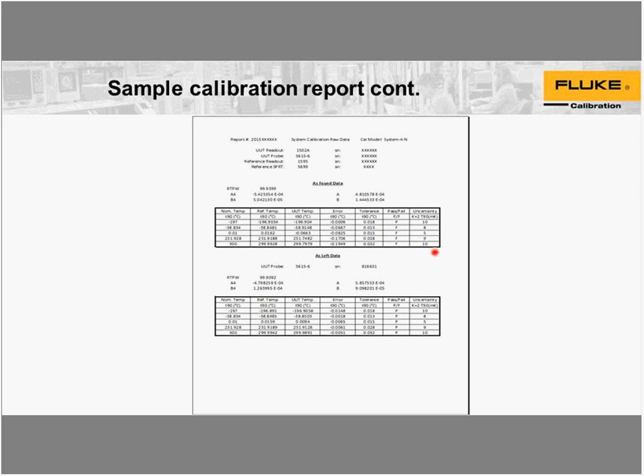So you know that by how measuring, we have a 10 millikelvin uncertainty at minus 200. We have an 8 millikelvin uncertainty at minus 38. We have a 5 millikelvin or millidegree uncertainty at 0 degrees. And then we have 9 and 30, or no, what is that, 10? Sorry, 10 at 300 degrees. Really small on the screen in front of me. I'm trying to solve.